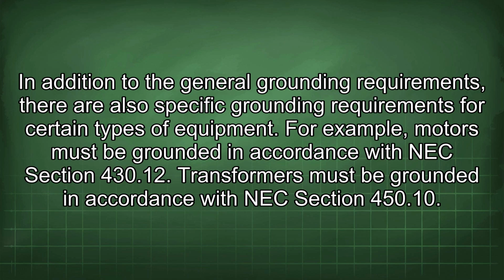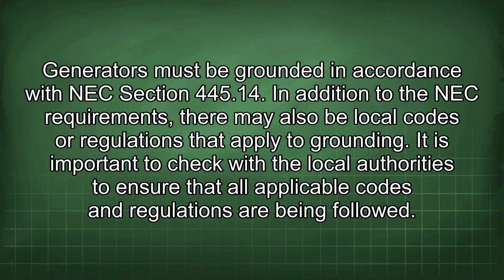In addition to the general grounding requirements, there are also specific grounding requirements for certain types of equipment. For example, motors must be grounded in accordance with NEC Section 430.12. Transformers must be grounded in accordance with NEC Section 450.10. Generators must be grounded in accordance with NEC Section 445.14. In addition to the NEC requirements, there may also be local codes or regulations that apply to grounding. It is important to check with the local authorities to ensure that all applicable codes and regulations are being followed.